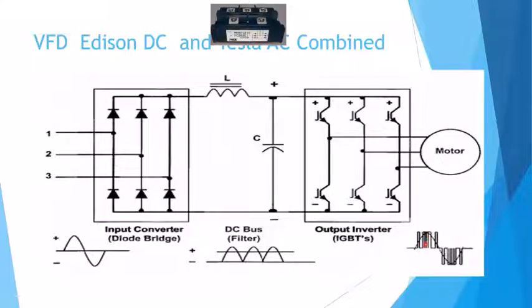It ended up creating a lot of noise in the motor. You could hear it. And then they went to, like I said, the insulated gate. We're able to get the firing circuit up. And a lot of them were roughly about 1,000 to maybe 2,000, what they call hertz. That's your carrier frequency of this pulse width in here, and how fast that pulses. Nowadays, you can buy them as high as a better VFD is in the 12 to 15,000 hertz range.